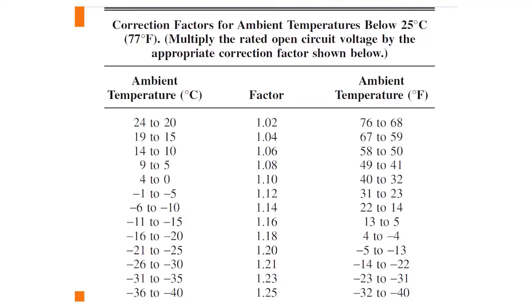So in fact, I was talking to somebody at lunch, and an area like the Midwest where they have very cold winters, very hot summers. And that's, again, you're stuck with this PV voltage changing with temperature, and it can be a real challenge to design a PV system to operate within the bounds of hot to cold. And so what we want to do is be able to not use an overly conservative temperature. And that's what this ASHRAE data is all about. And there's the website where you can go to get the ASHRAE data.